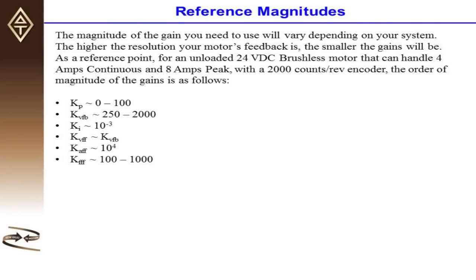As a reference point, for an unloaded 24 volt DC brushless motor that can handle 4 amps continuous and 8 amps peak, the order of magnitude of the gains is as follows. KP is roughly between 0 and 100.